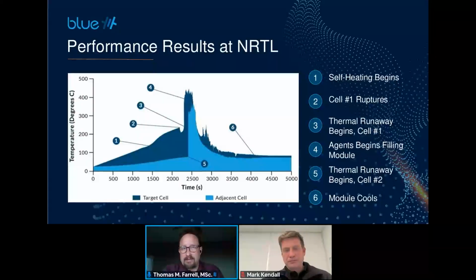And about 8 seconds later in this test at marker 4, blue was released into the system. And in this particular one, we used a fully passive system. So it responded based on temperature, but there was no controller involved. And we didn't command the system to fire. We left it pressurized and it released on its own.